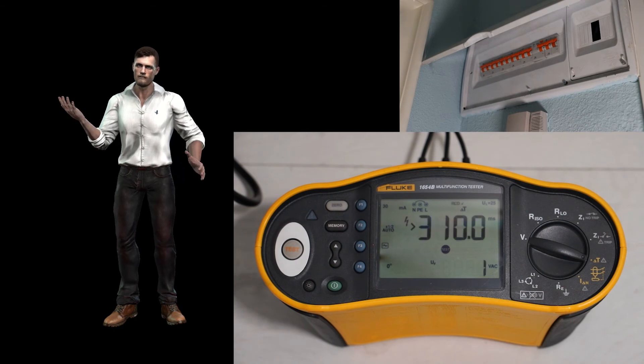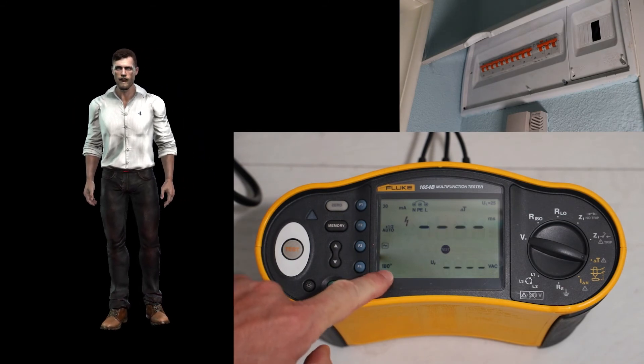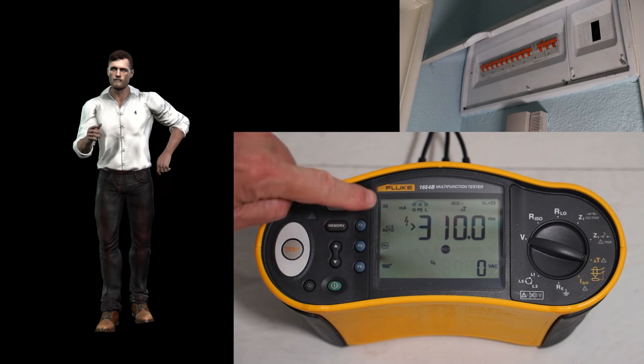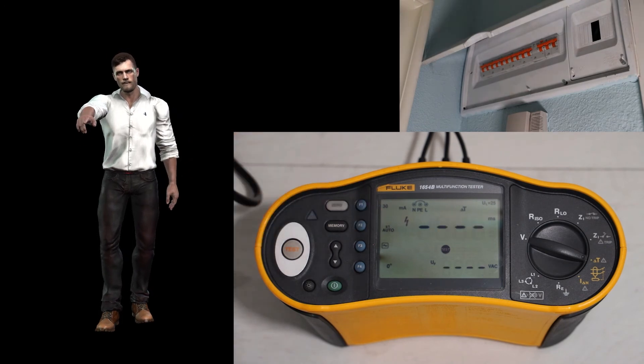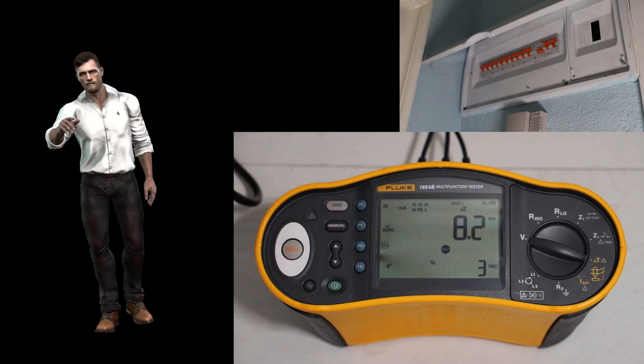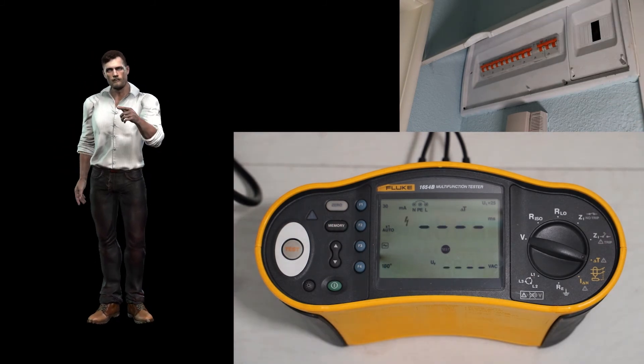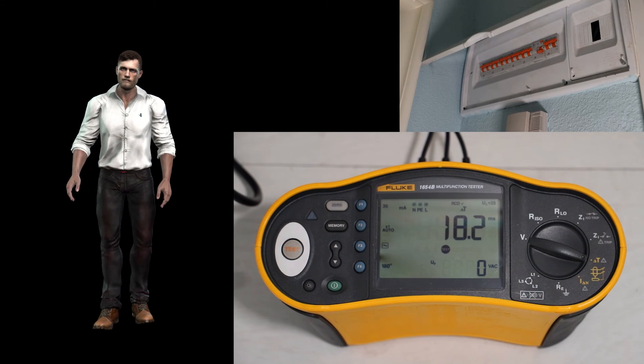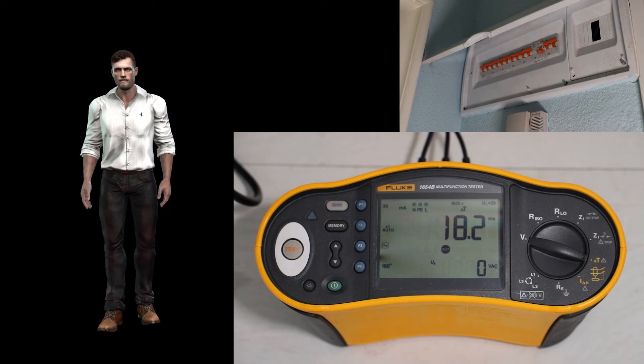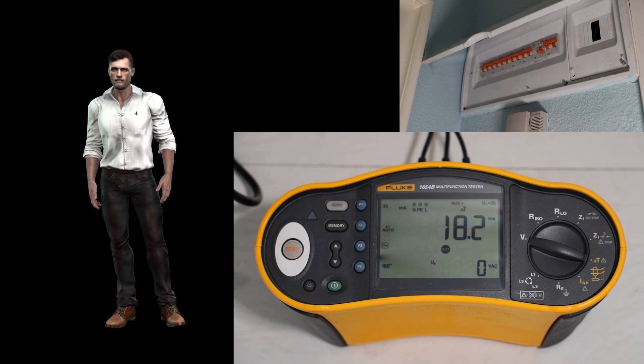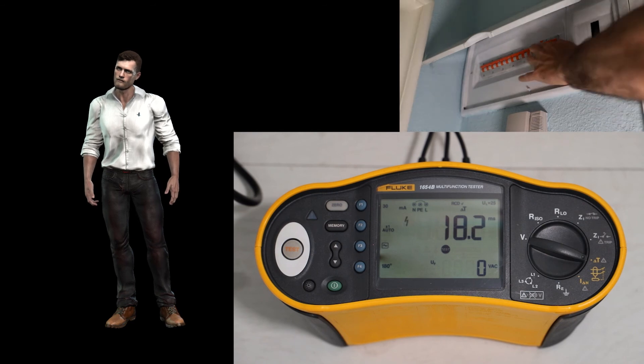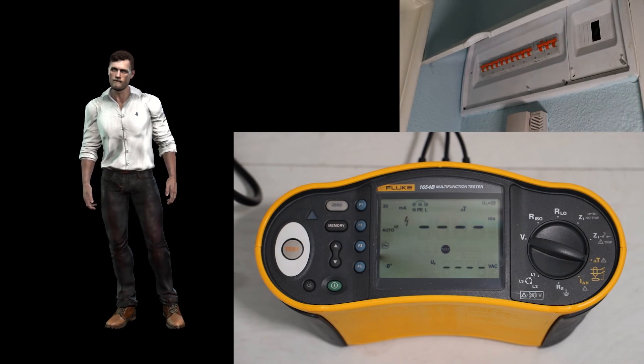We start with the positive and negative cycle at half the nominal current, and the differential should not trip. Then the instrument will proceed automatically with the tests with the positive and negative cycle at the nominal current, and if the differential protection works correctly, it should trip in both tests. If that is the case, we will have to reset the differential protection, and at that moment the instrument will detect that there is voltage again and will continue with the test automatically.